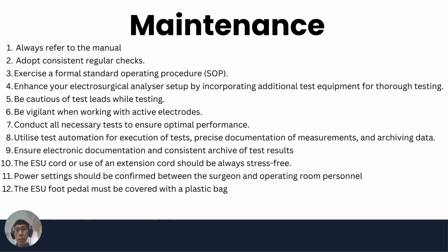Thirdly, exercise a formal standard operating procedure (SOP). In the absence of the manufacturer's service manual and inspection method, the medical facility remains accountable for selecting and standardizing a testing approach. It's crucial to quantitatively assess the usability of the electrosurgery generator by comparing against the manufacturer's specifications, or enhance your electrosurgical analyzer setup by incorporating additional test equipment for thorough testing. Many manufacturer performance inspection protocols necessitate electrical safety assessments such as ground wire resistance and chassis leakage tests. To ensure easy completion of the electrical safety component of the performance inspection, have an electrical safety analyzer readily available.